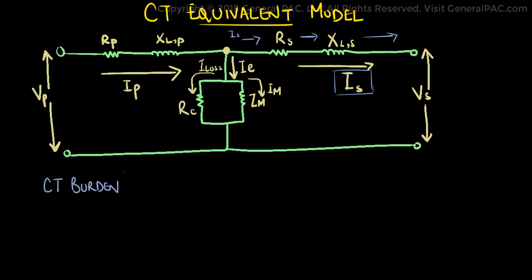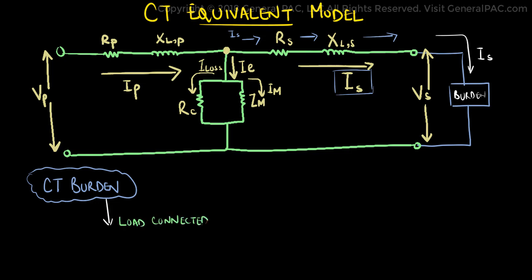Another important parameter to consider is the CT burden which can be defined as the load connected to the secondary side. The CT burden is typically relay and meter impedance, as well as impedance of the wires that connect relays and meters.